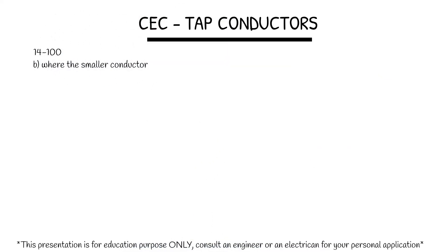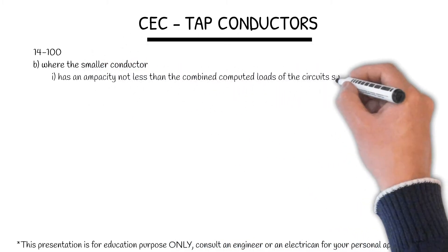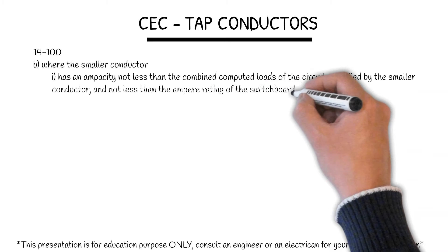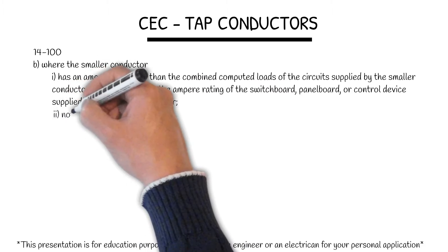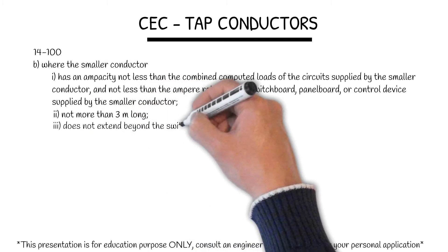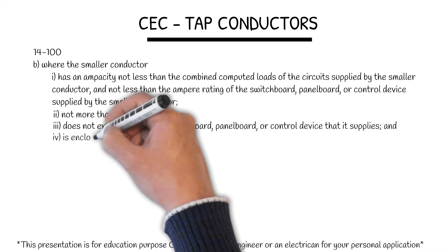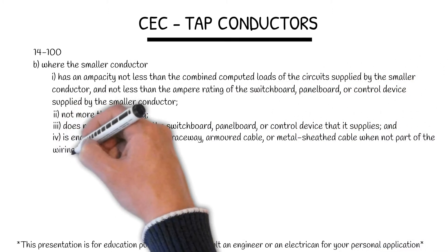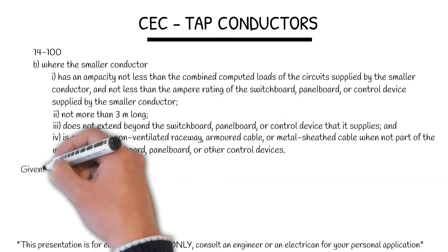14-100 Subrule B: the smaller conductor has an ampacity not less than the combined computed loads of the circuits supplied by the smaller conductor, and not less than the ampere rating of the switchboard, panelboard, or control device supplied by the smaller conductor. Not more than 3 meters long, does not extend beyond the switchboard, panelboard, or control device that it supplies, and is enclosed in a non-ventilated raceway, armored cable, or metal sheath cable when not part of the wiring in the switchboard, panelboard, or other control devices.